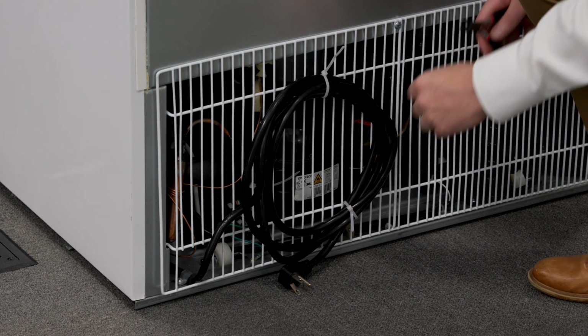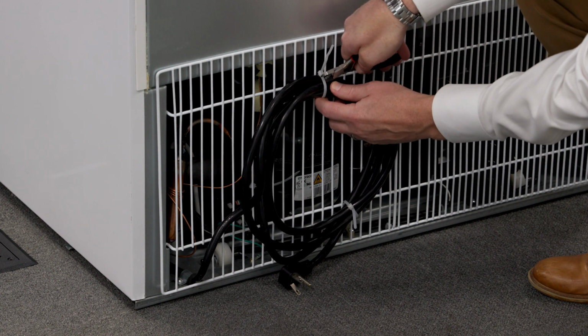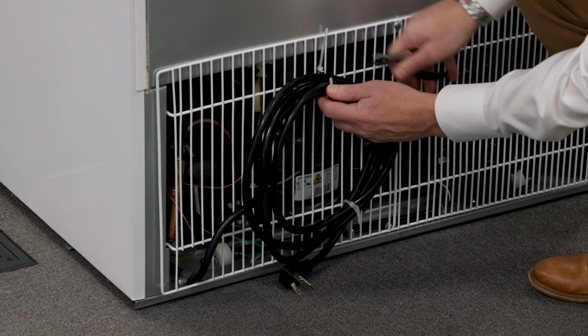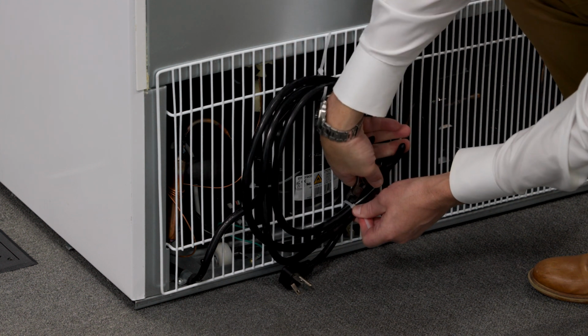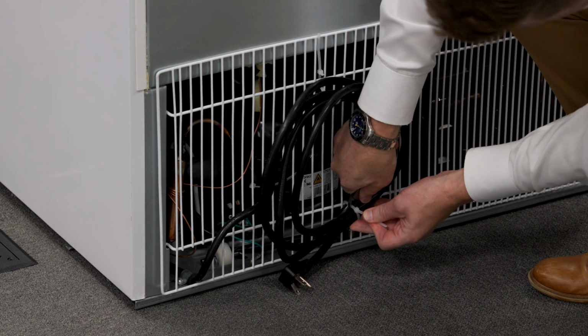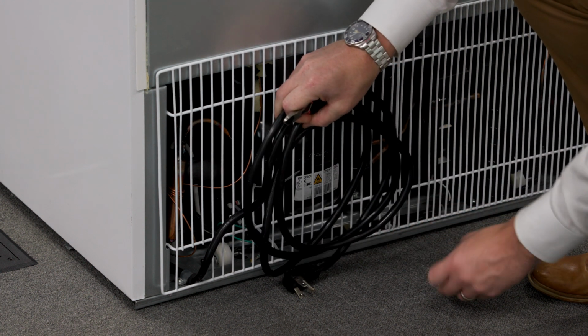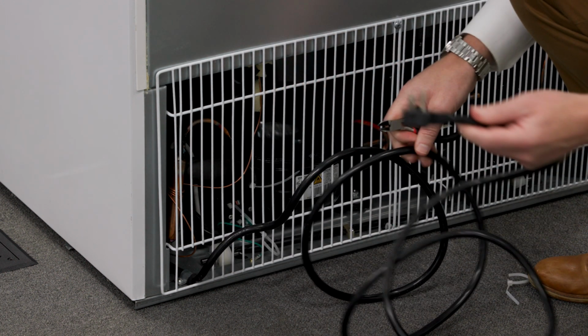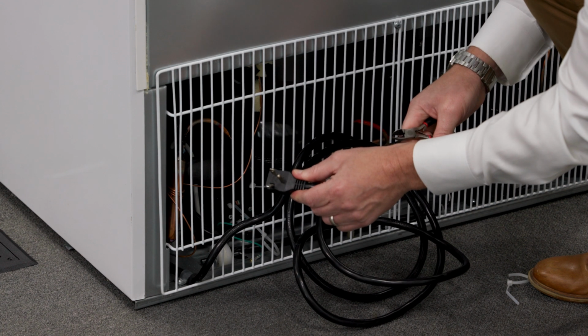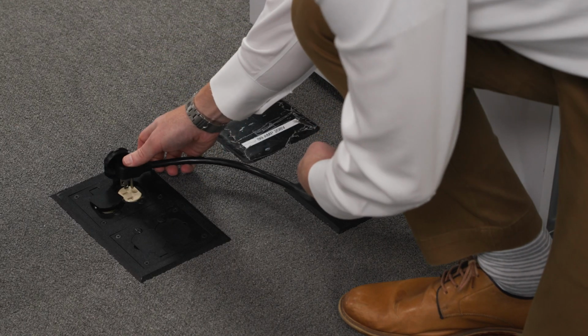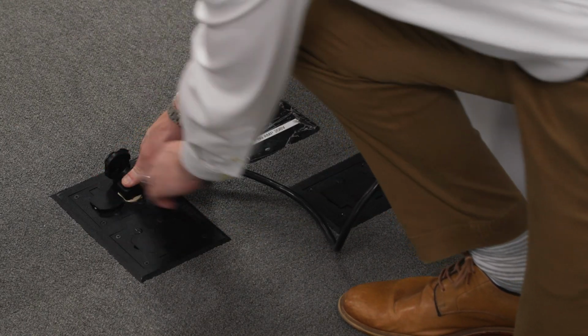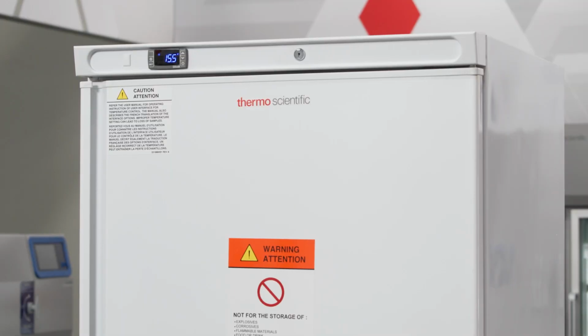Prior to plugging the unit in, carefully review the electrical connections, considerations, and warnings outlined in your user manual. Do not remove, under any circumstances, the grounding prongs from the three-prong power cord supplied with the unit. When it has been determined that your facility meets the electrical connection needs, plug the unit in and let it run for 2 to 3 hours. Once the unit is plugged in, the display screen will turn on and display the unit temperature information.